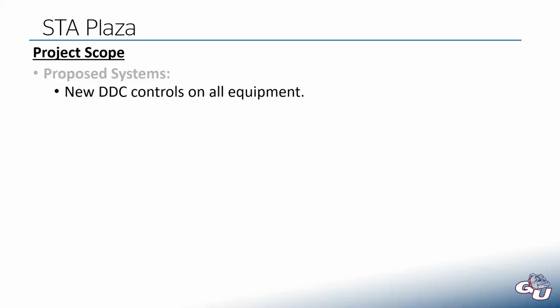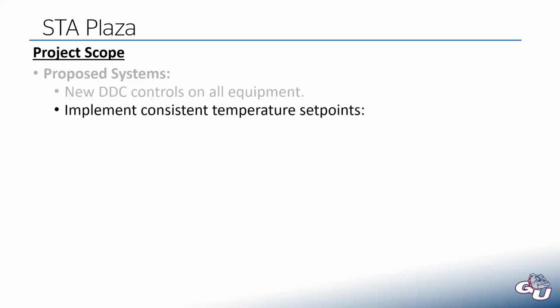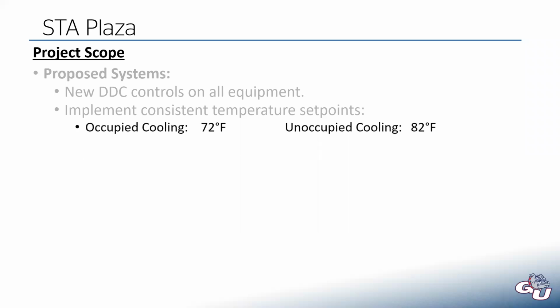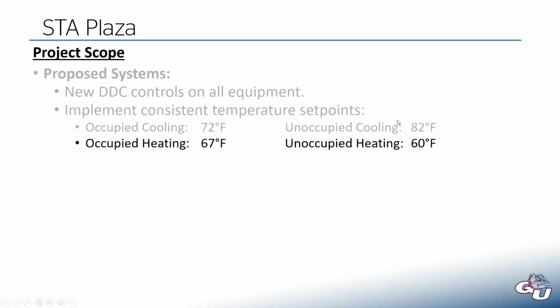What we proposed to do, and what we did do, well, I already mentioned they wanted new DDC controls on all their equipment. We implemented a consistent set of temperature set points throughout the building. So we worked with the client and they told us, we want to maintain our building at 72 in the summer. And then when we're unoccupied in the summer, let it warm up to 82. And then 67 in heating mode. If we're in unoccupied heating, 60 degrees.